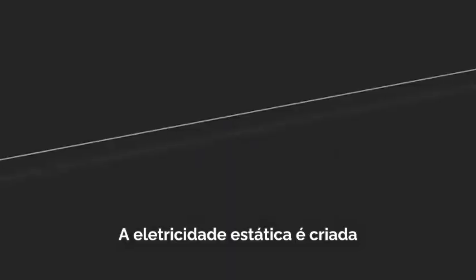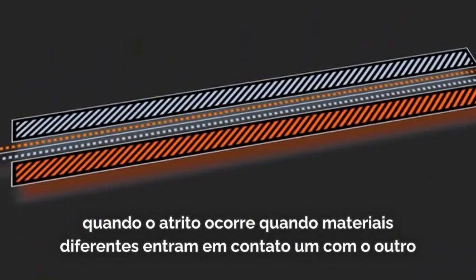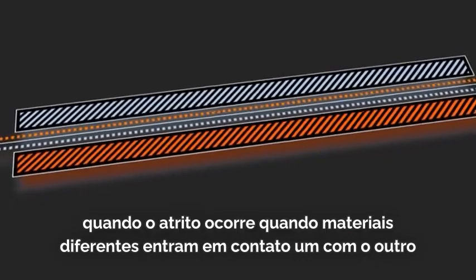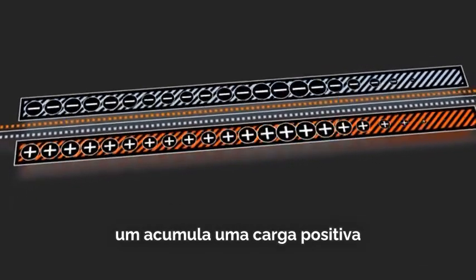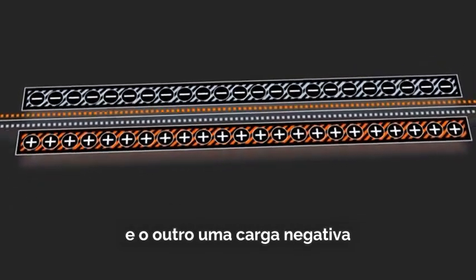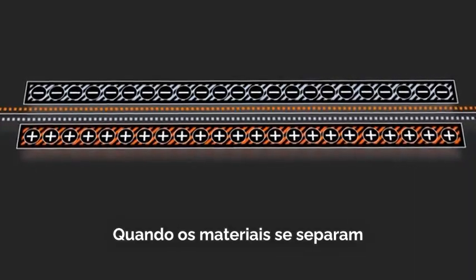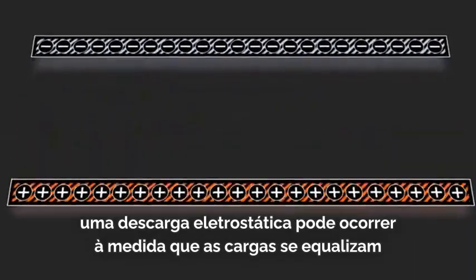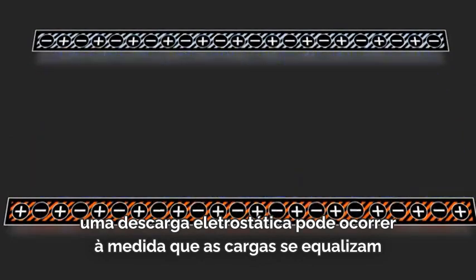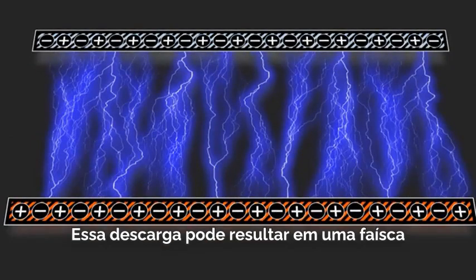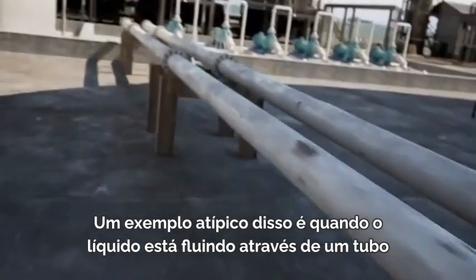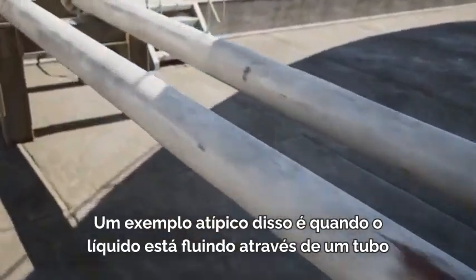Static electricity is created when friction occurs, as dissimilar materials come into contact with one another. When this happens, one accumulates a positive charge and the other a negative charge. When the materials separate, an electrostatic discharge can occur as the charges equalize. This discharge can result in a spark. A typical example of this is when liquid is flowing through a pipe.